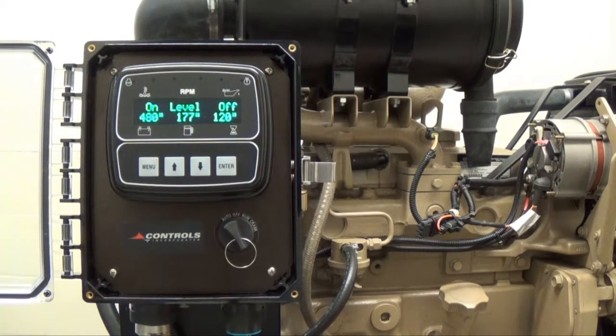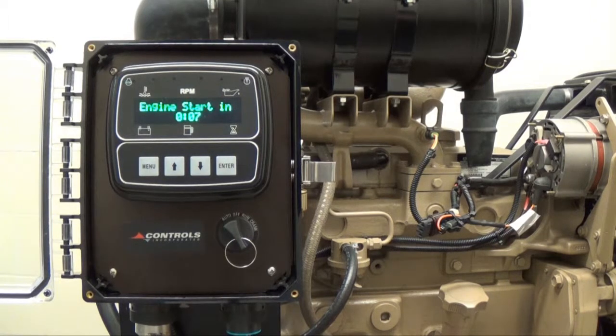In this video, the engine will start and the pump will run according to level transducer settings programmed in the configurable menu. Please watch our Controls Incorporated Level Transducer with Failsafe Float video to learn about start and stop set points for engine operation. When the pit levels rise above the start point, the controller will immediately power up and begin a countdown to start the engine.